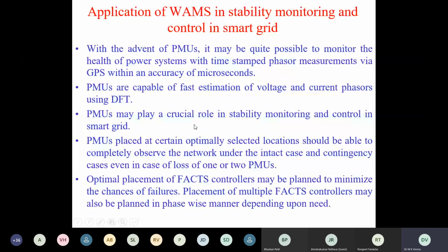PMUs may be placed at certain optimally located places, and it is not necessary that you put a PMU at each and every bus to perform measurements. But with PMUs placed at certain buses, the system may be made completely observable. What do you mean by completely observable? Means with limited PMUs, you can measure voltages at all the buses. You can measure current flowing through all the lines, and you can completely analyze the whole system. So there is no need of putting PMUs at all the locations, all the buses, but at certain optimal buses you can put, and by that you can do the real-time analysis of the system, and you can make the whole system completely observable.